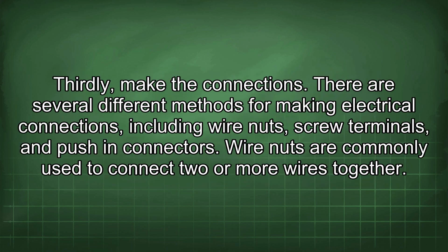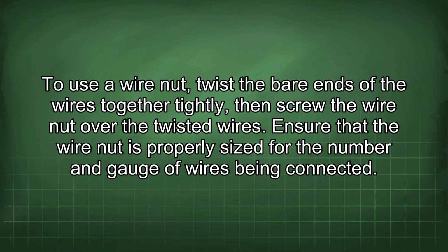Thirdly, make the connections. There are several different methods for making electrical connections, including wire nuts, screw terminals, and push-in connectors. Wire nuts are commonly used to connect two or more wires together. To use a wire nut, twist the bare ends of the wires together tightly, then screw the wire nut over the twisted wires. Ensure that the wire nut is properly sized for the number and gauge of wires being connected.